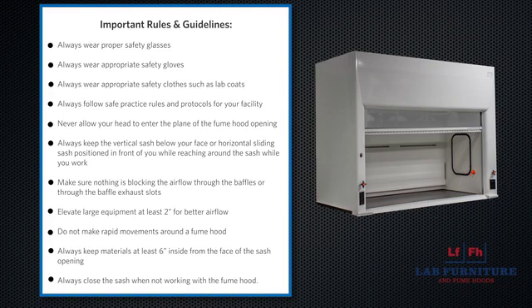Always move your hand in a direct line of motion. Always keep materials at least 6 inches inside of the face of the sash. And always close the sash when not working in the fume hood.